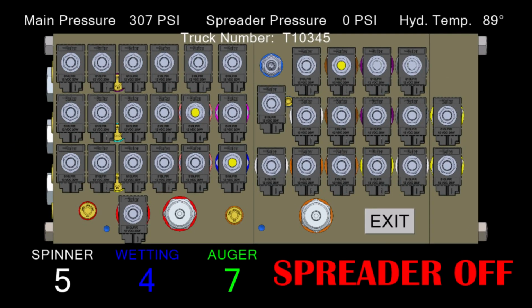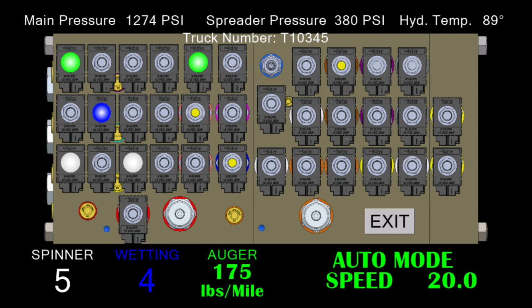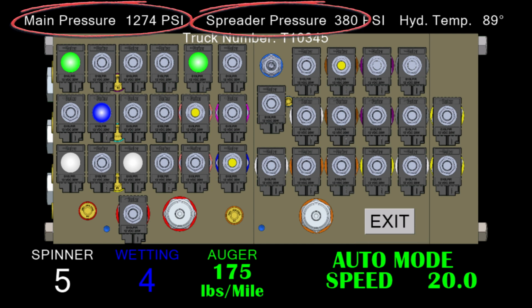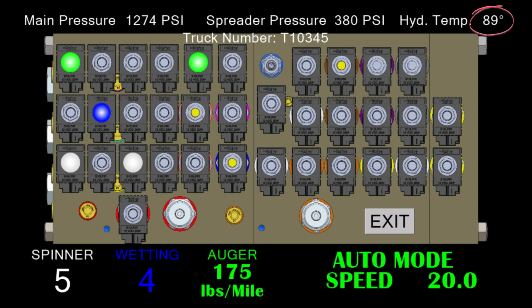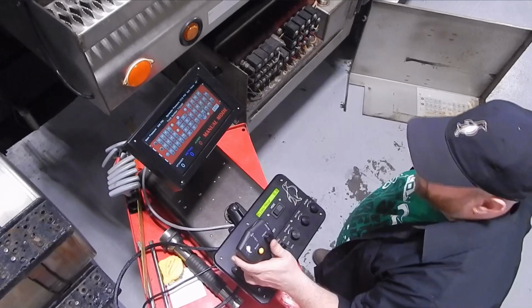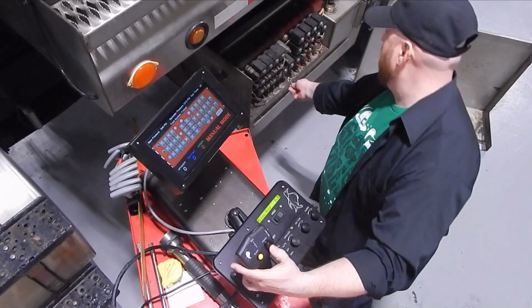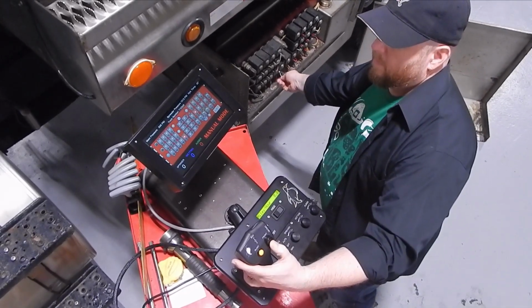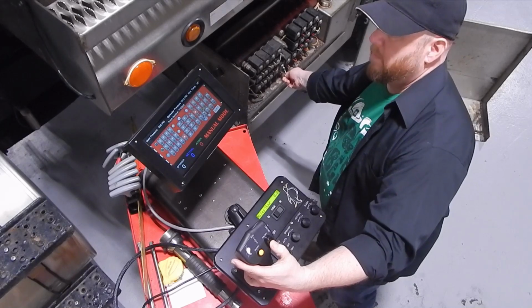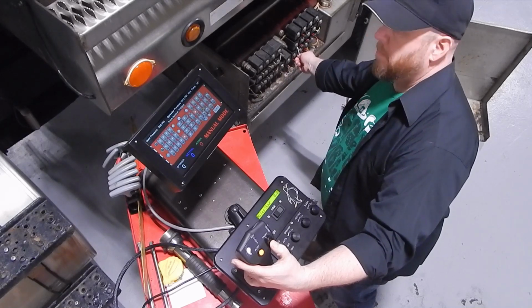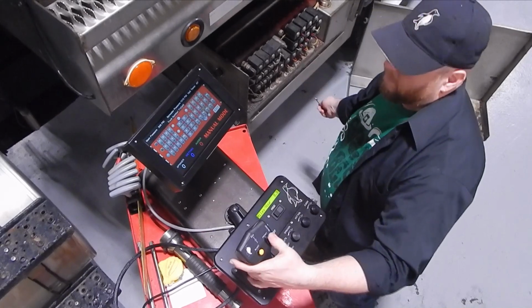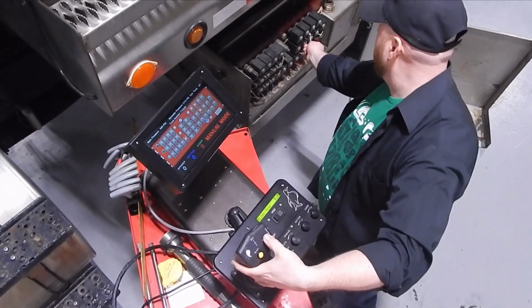Also included in the coil energization screen are speed, spreader status, pressures, and hydraulic oil temperature. Since it shows coil functions in real time, automatic functions can be easily tested using Speed Sim. Cylinder function energization can be checked using the troubleshooting cable to relocate controls next to the hydraulic manifold.